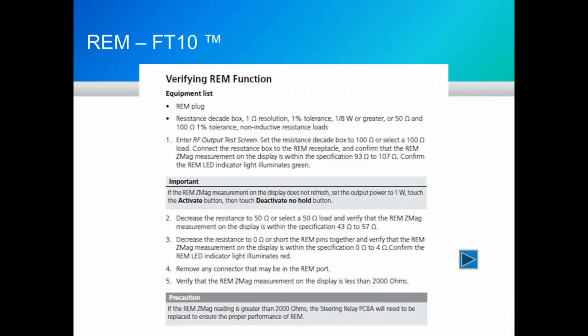Big change in how we test REM. With the Triad, with the FX, with earlier units, we used to start at 120 ohms, connect the generator to our test circuit, whether it was a decade box or whatever, and we would increase the resistance until we got an alarm. We record that alarm, then we would back down, record the lower limit, which typically would happen around 4 ohms or so with a Force Triad.